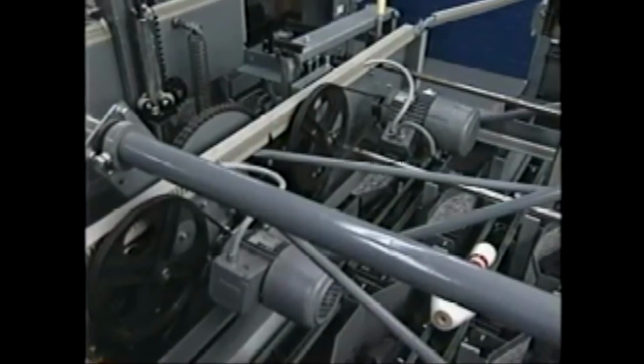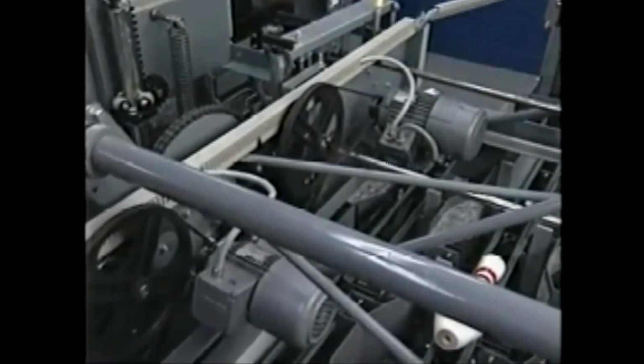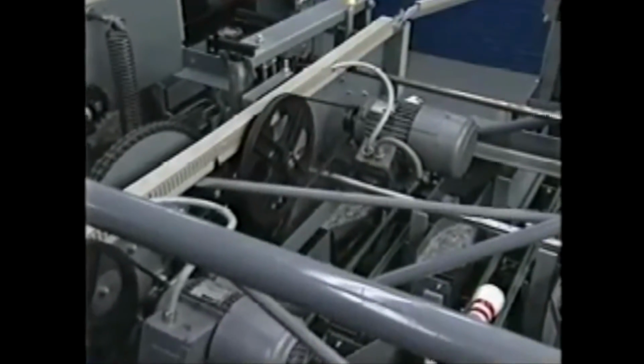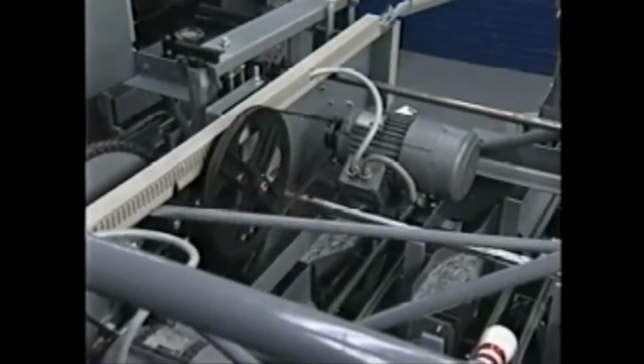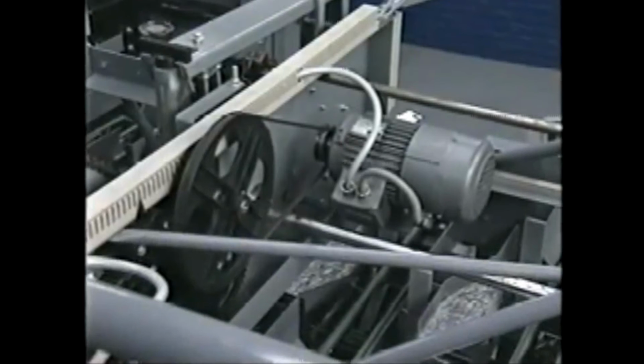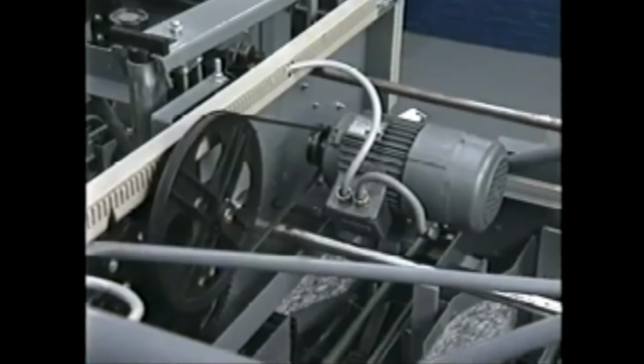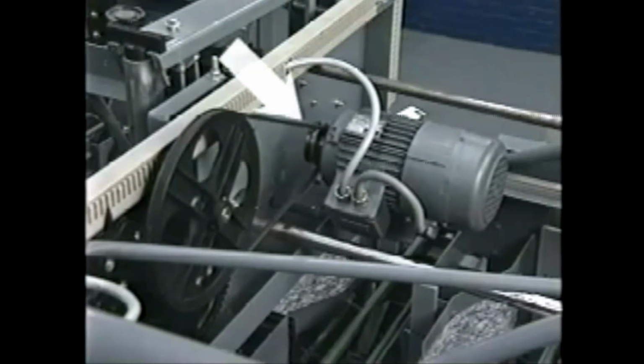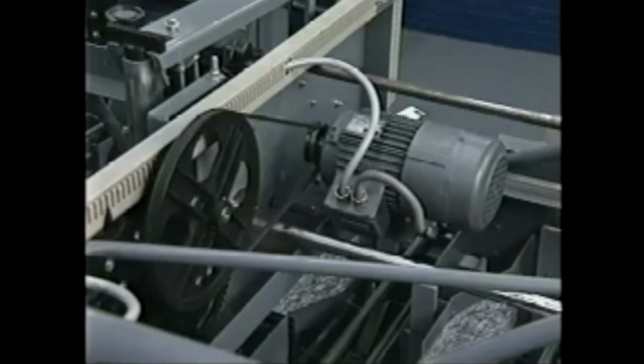Check all the V-belts for wear. Look for cracks, splits, or motor bounce. Wipe all the belts with a dry cloth while you inspect them. Be sure to look closely at the table motor drive belt. If this belt fails, it could cause the table to suddenly drop. This could severely damage the machine or cause personal injury.